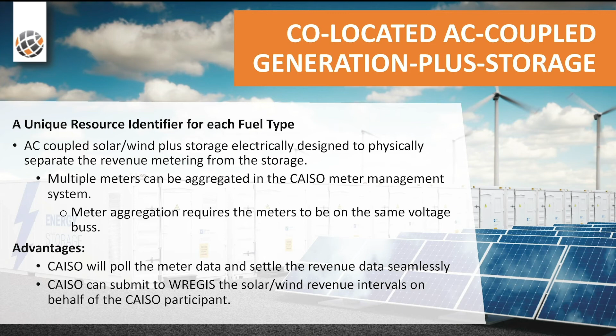That metering would need to be on the same voltage buses, usually your 34.5 bus if you're grid connected. The advantage is that the ISO would poll the meters directly and submit that data into settlements, and you can request the ISO to report those intervals of energy into the WREGIS system for your credits. So this here is a simplified single line drawing depicting what I was mentioning earlier, with the storage on the left and the solar on the right.